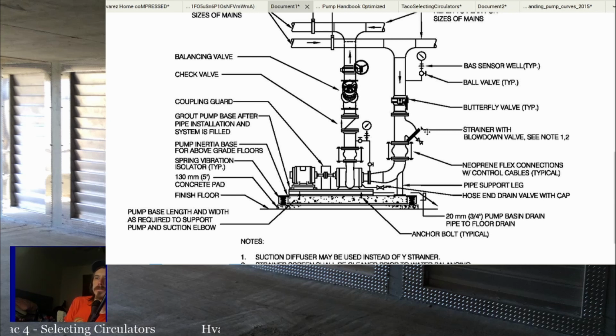A strainer before the pump is generally a good idea to keep anything from getting into it, but you need to be very careful putting a strainer before the pump, okay? Because a strainer is going to block flow to the suction side of a pump, and you never want to completely block or cause enough restriction in the flow that you end up cavitating. So if you do put a strainer before the pump, it's extremely important that it's maintained and that it stays clean. If you are unsure, the best thing to do, don't put a strainer in.